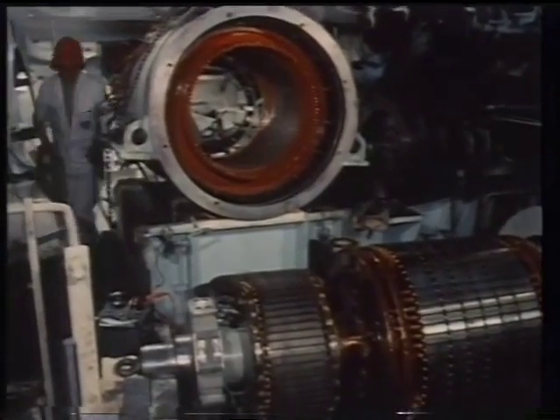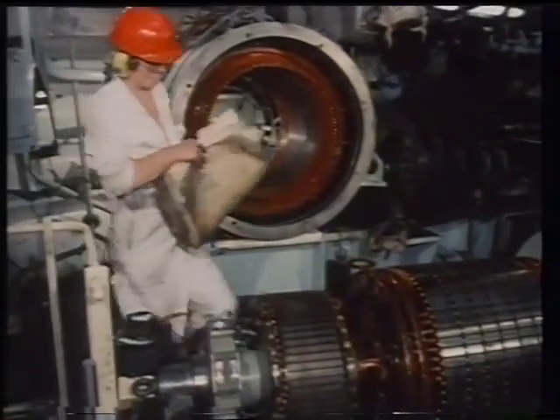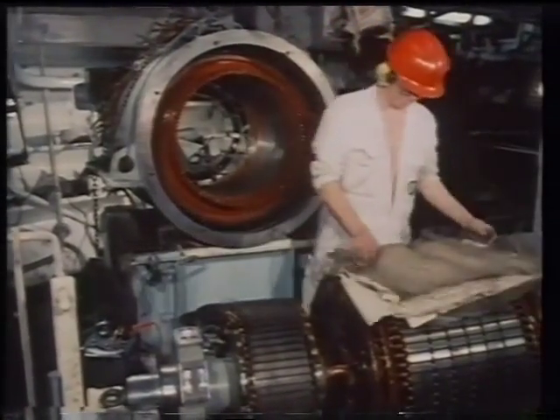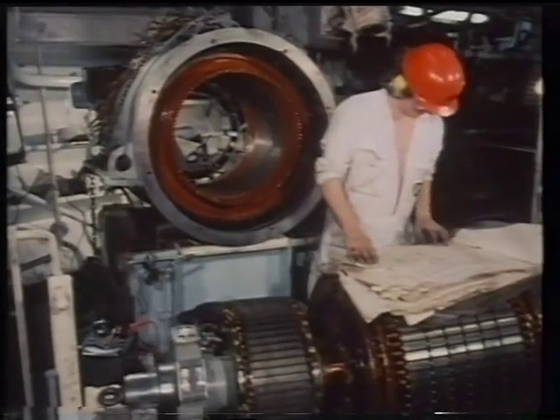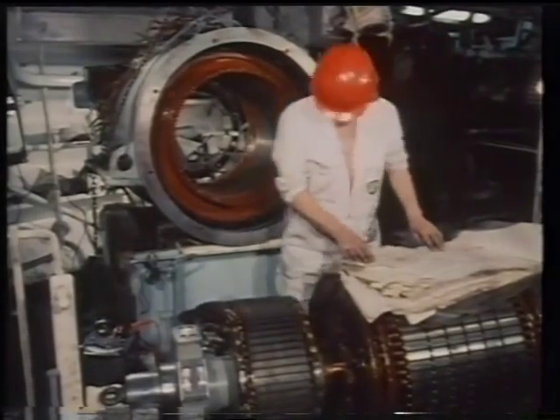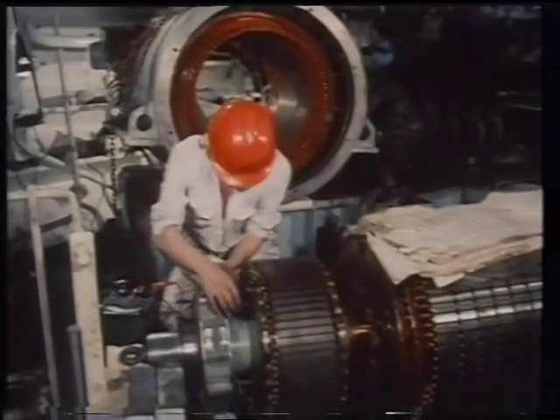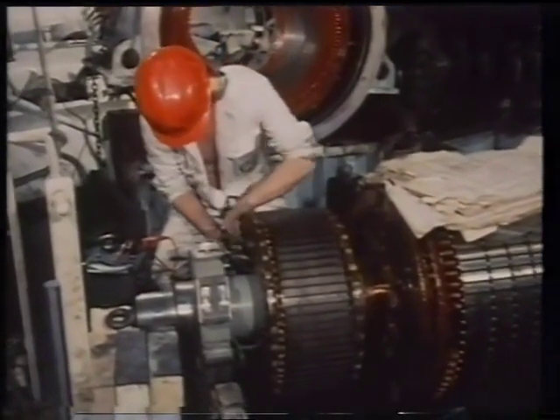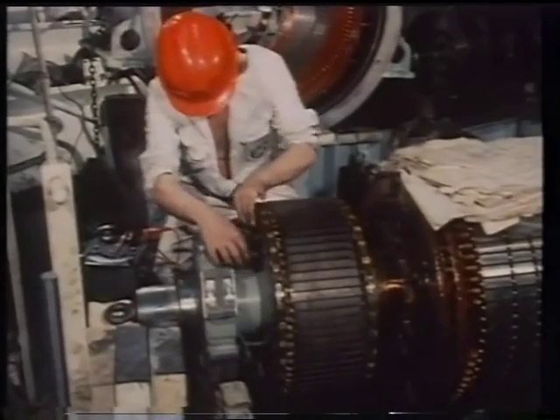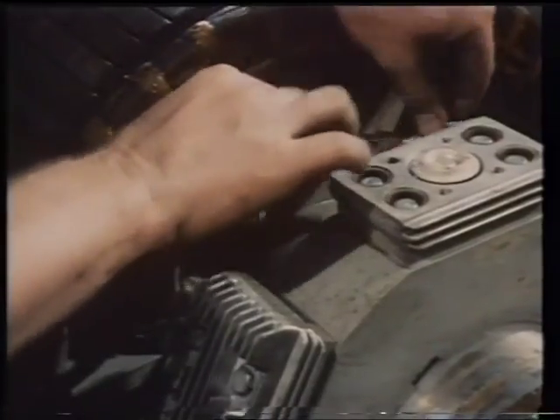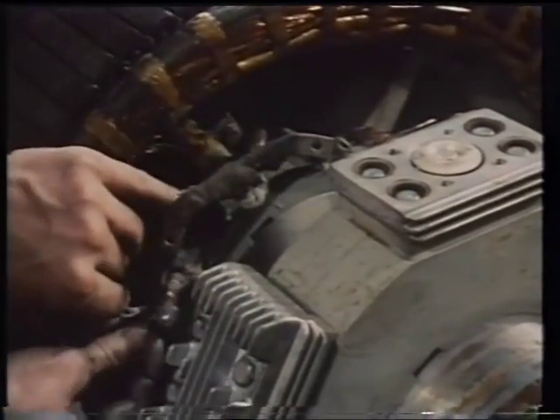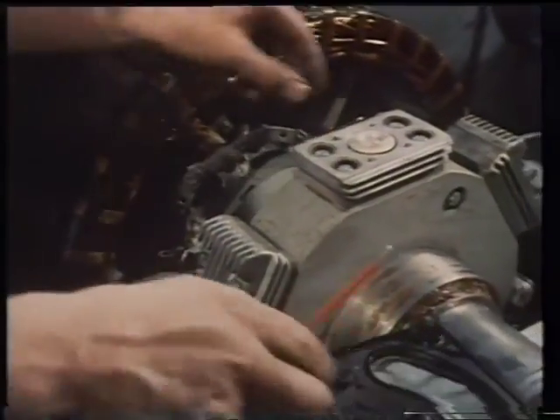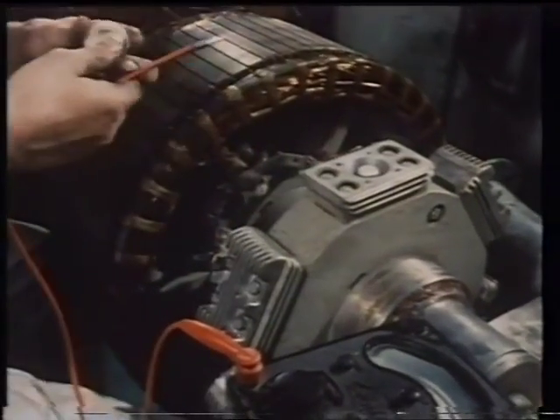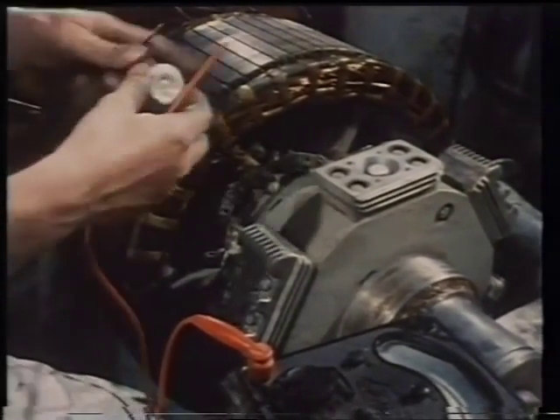In order to test for a possible short circuit fault, which the high excitation current suggests, the three circuits must be separated and tested independently. This means the alternator must be opened up to reveal the wiring involved. Here we've stripped out the alternator rotor for easy demonstration, but of course, there's no need for this when the job is carried out. In practice, first separate the wiring to disconnect the diodes, the capacitor, the resistor and the rotor coils. Here this has been done already.